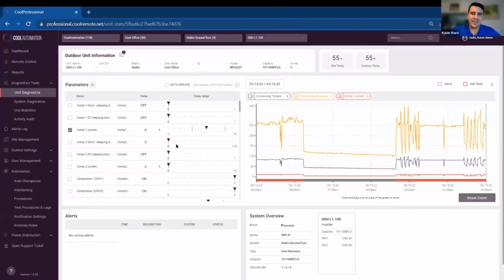Hey again, everybody. In this example, I'd like to start by showcasing the application's ability to measure your diagnostic parameters from your VRF system. We're actively pulling this from the VRF system itself and looking real time at, in this case, a Daikin outdoor unit. Each of the parameters that you can see from your service check tool will appear here and are tracked and trended for up to a year.